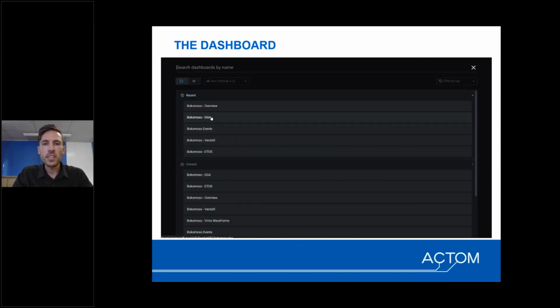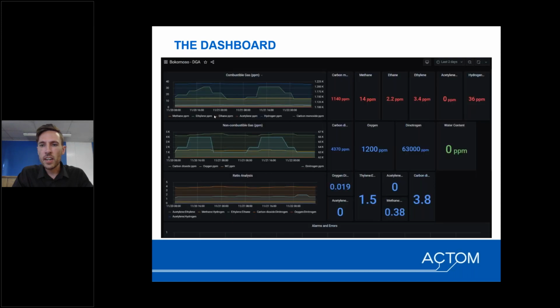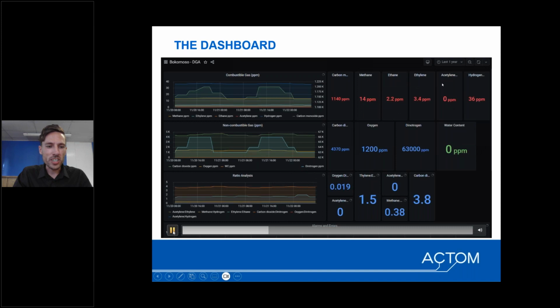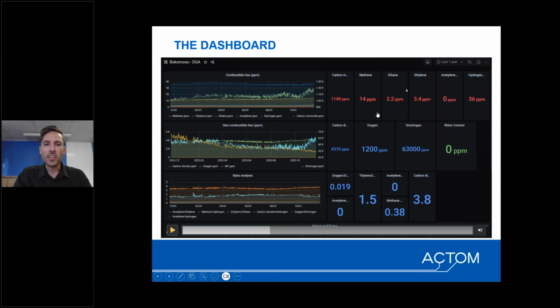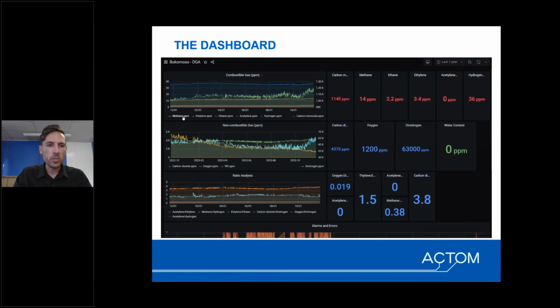We then go to the dissolved gas analyzer. Here we have our combustible gases at the top, because those are usually the most important ones you want to look at. And then our non-combustible gases here at the bottom. These are live figures, so you can set it to an interval that works for you.